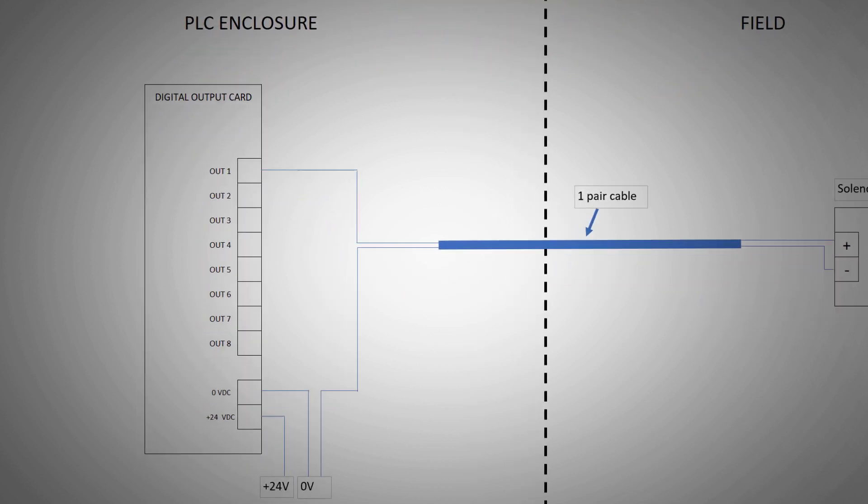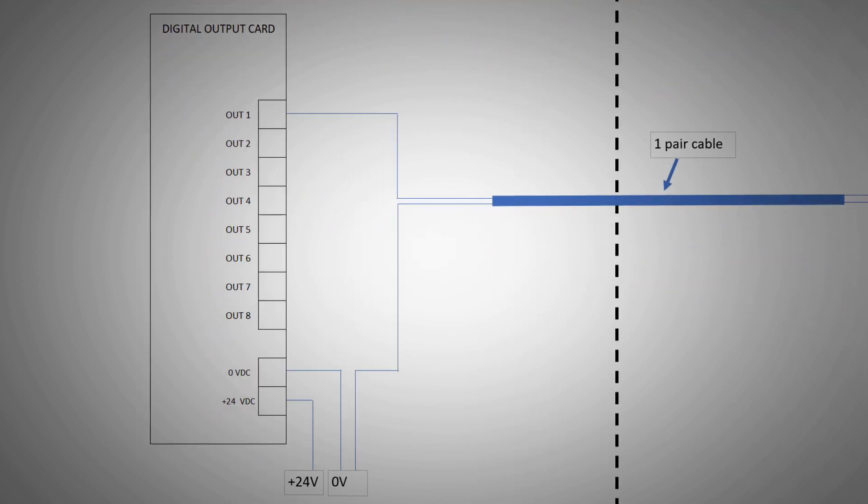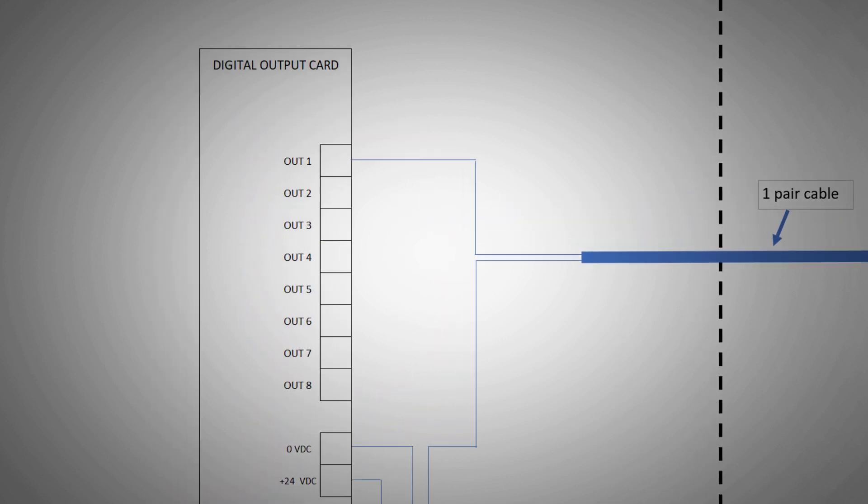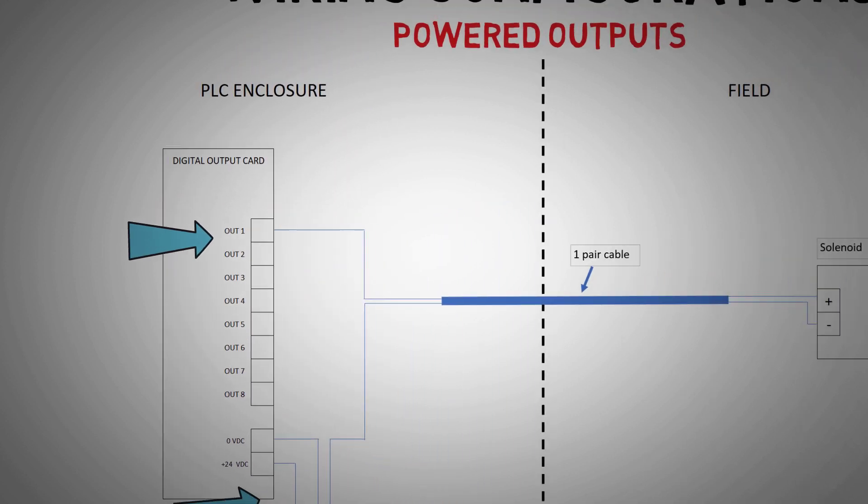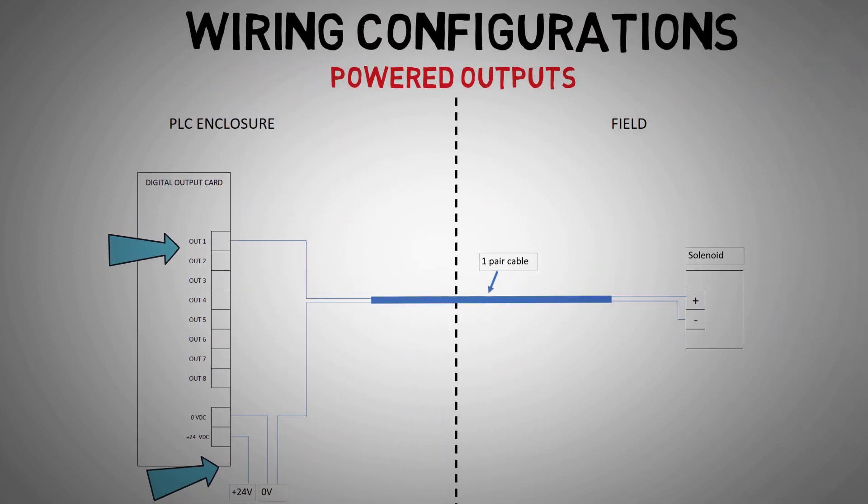First, the output card is powered by 0 volts and 24 volts. The solenoid is powered directly from output one of the PLC via a one-pair cable. The 0 volts is then terminated back in the PLC enclosure.